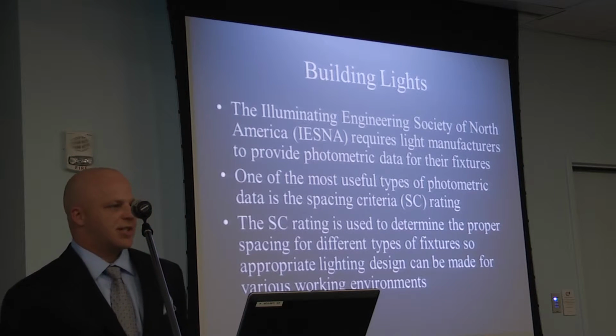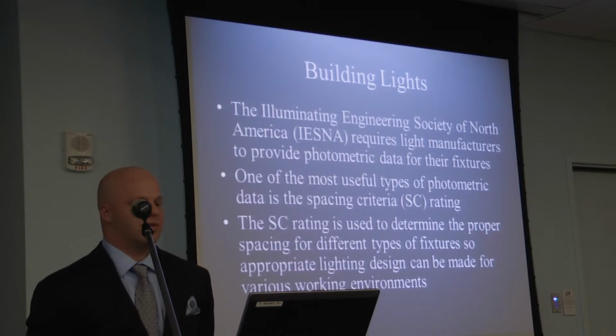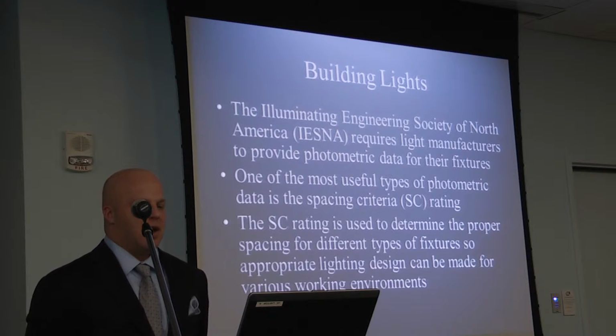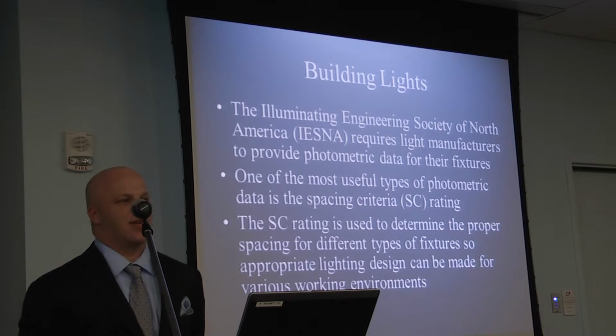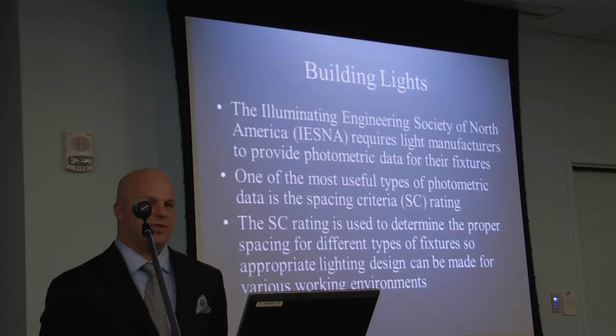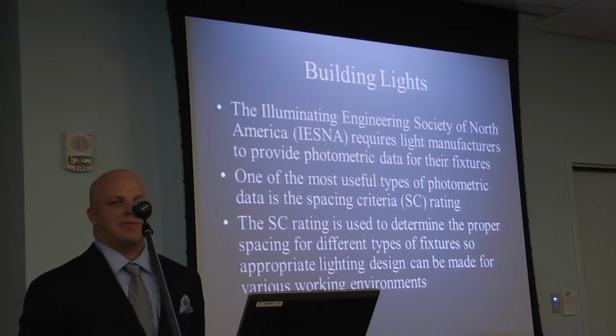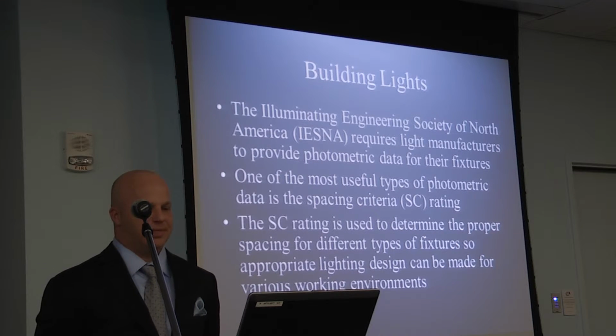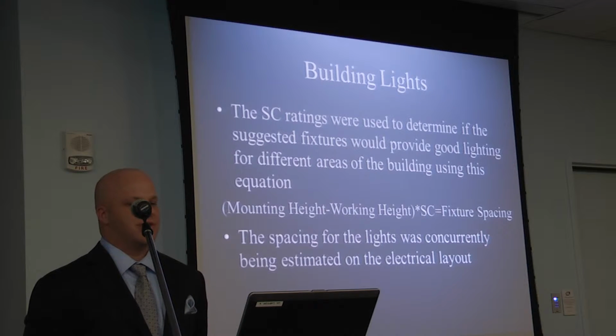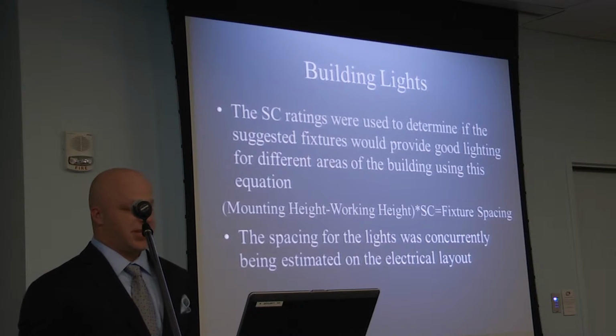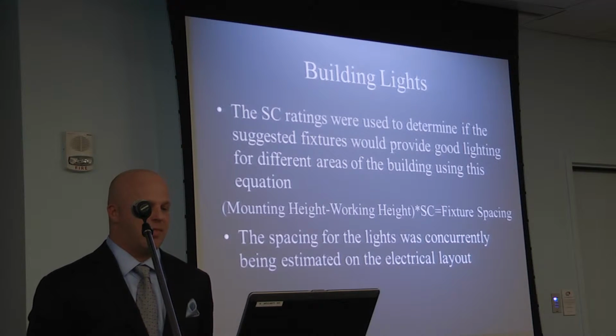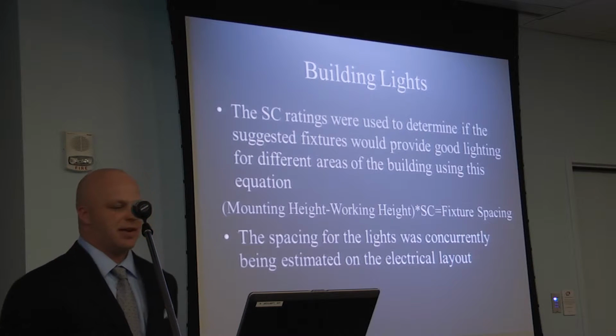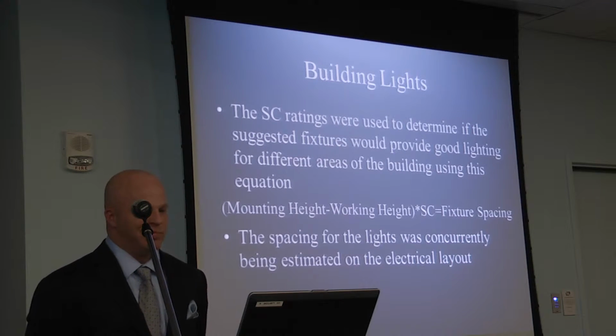The Illuminating Engineering Society of North America requires light manufacturers to provide photometric data for their fixtures. One of the most useful types of photometric data is the spacing criteria, or SC rating. SC rating is used to determine the proper spacing for different types of fixtures, so appropriate lighting can be designed for various work environments. The SC ratings were used to determine if the suggested fixtures would provide good lighting for different areas of the building using this equation. The mounting height of the fixture minus the working height times the SC rating equals maximum fixture spacing.